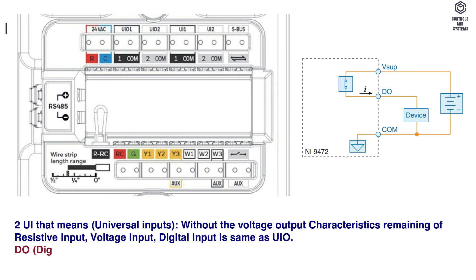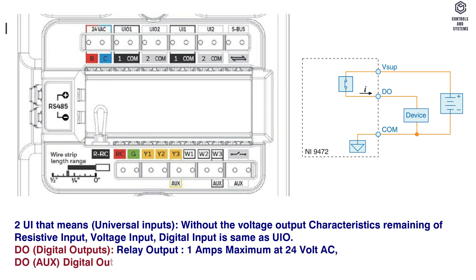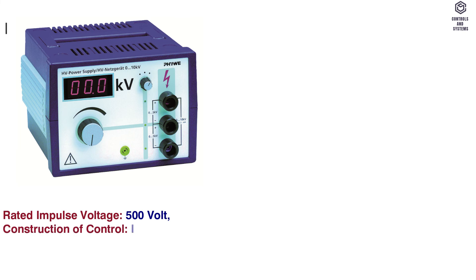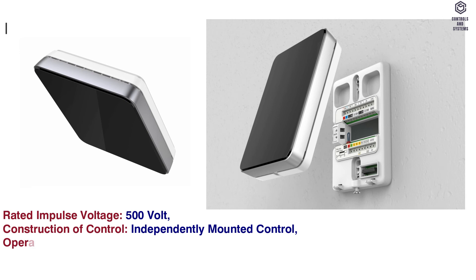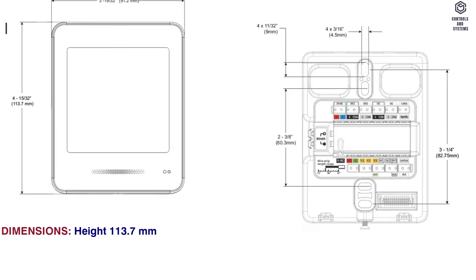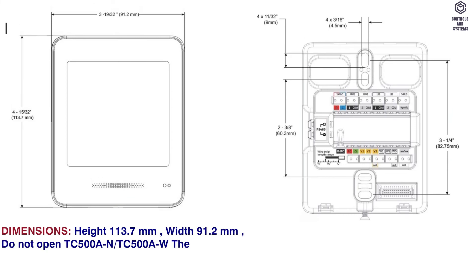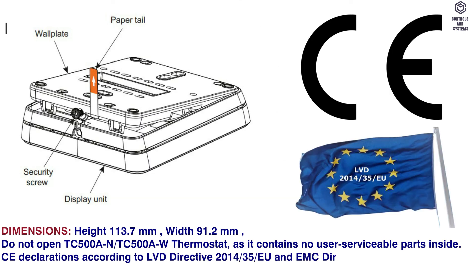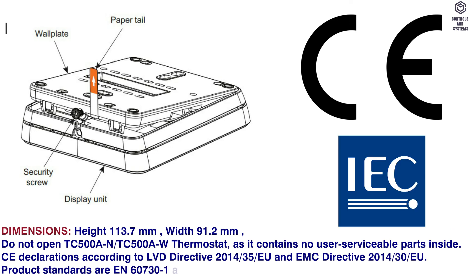Digital outputs (DO): relay output — 1 amp maximum at 24V AC. Digital outputs auxiliary (DO aux): relay dry contact — 1 amp maximum at 24V AC or DC. DO electrical characteristics: rated impulse voltage 500V, construction — independently mounted control, operation method — Type 1 action, pollution degree 2, purpose of control — operating control. Dimensions: height 113.7 mm, width 91.2 mm. Do not open the TC500AN or TC500AW thermostat as it contains no user-serviceable parts inside.